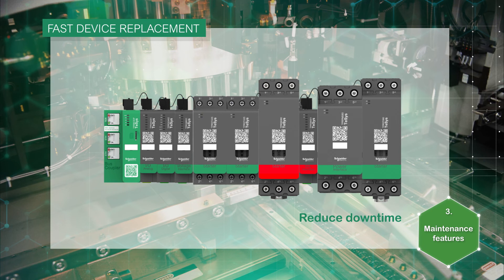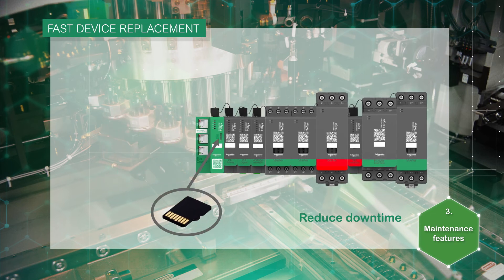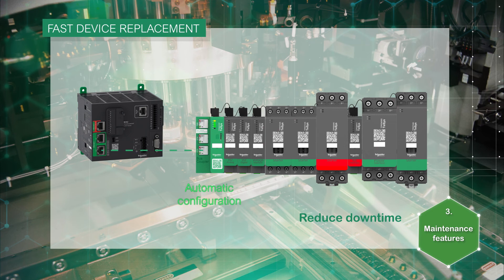The same procedure applies to the bus coupler. Insert the SD card to reload the saved configuration, or use the FDR through the PLC. No automation or network configuration skills are required. Once powered, the bus coupler automatically retrieves the configuration of the island including the network settings and is operational in less than 2 minutes.